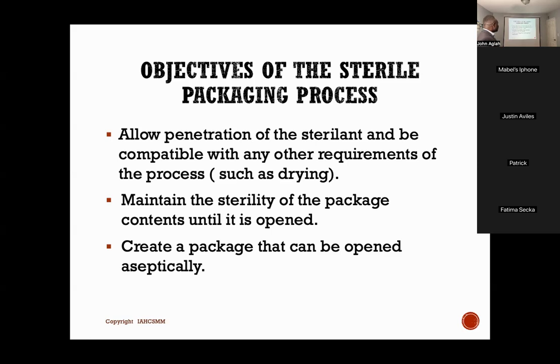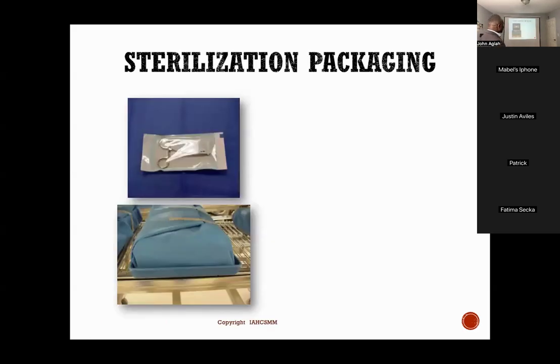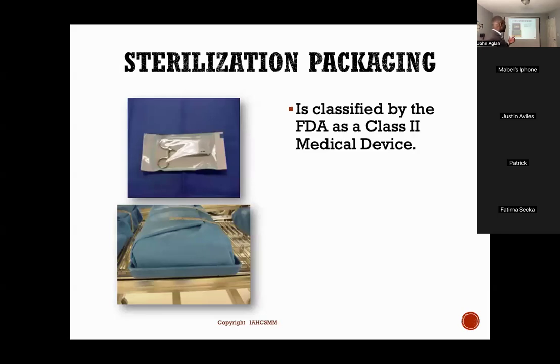Create packages that can be opened aseptically. So the package is done in a way that when the trays get to the OR, it can be opened in a way that the OR room will not compromise what is in the contents. Okay, we're going to look at 3 different types of packages. Sterilization packaging is classified by the FDA as a Class 2 medical device. A Class 2 medical device means that the package has what it takes to cause some form of issues or dangers to patient care.